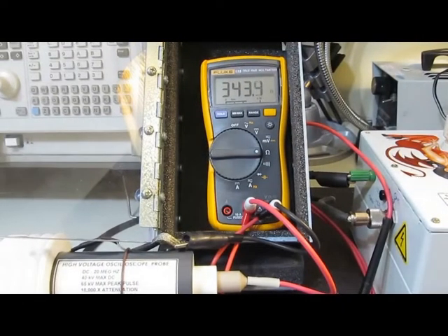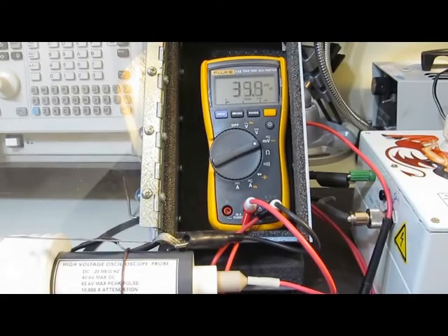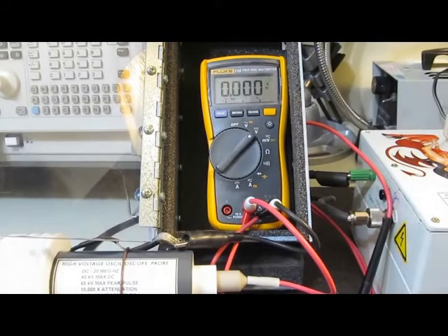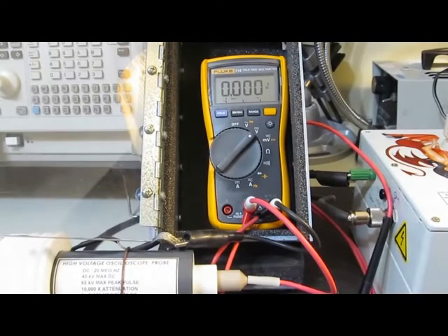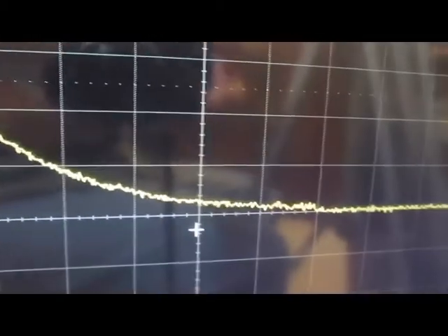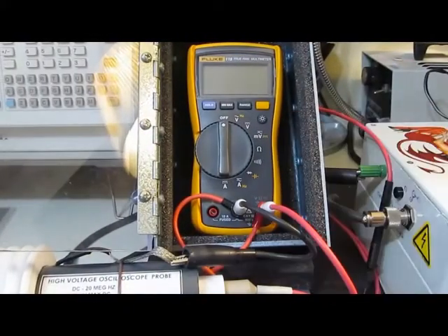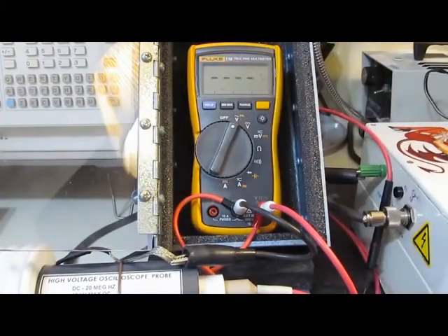If you want to see what this looks like here, yeah, it's 5kV per division and 50 microsecond full width half-height. Okay, we'll go ahead and check it out here. We can see we're at 5,000 volts per division and still 50 microseconds per division. This will be our next transient, it's roughly 12,000 volts, and you can see it's roughly a 50 microsecond full width half-height. Again, five transients positive and negative.